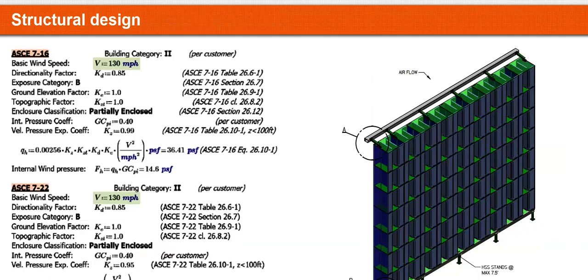And just to reiterate, in a lot of specs, even for outside plenums, I see a lot of shortcuts saying it needs to be self-supporting. When you get to the size of these openings, the size of these solutions, and you're attaching to a massive building, and you have a pressure rating, you have a wind load, you have seismic, there is no such thing as self-supporting. You're going to have to spend some money, whether within your office or through a manufacturer that has the capability to do it, to see how to properly support under given loads based on a particular jurisdiction or area. So they go hand in hand.